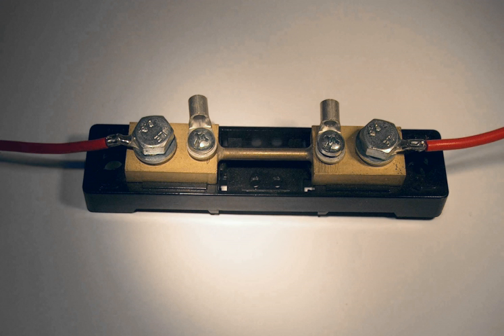Where the circuit is grounded on one side, a current measuring shunt can be inserted either in the ungrounded conductor or in the grounded conductor. A shunt in the ungrounded conductor must be insulated for the full circuit voltage to ground. The measuring instrument must be inherently isolated from ground or must include a resistive voltage divider or an isolation amplifier between the relatively high common mode voltage and lower voltages inside the instrument.